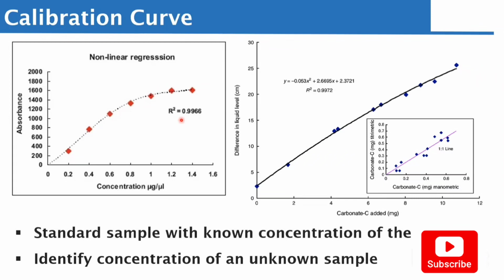And obviously, this leads me to also say that each control sample can come with its own calibration plasma or calibration sample, as the case may be. So one other reason why we repeat the calibration is if we find out that the lot number of the current control sample is different from what is already inputted and accepted in the system. It means you then need to redo another calibration which is consistent with the current control sample. I hope that makes sense. Let me repeat what I said. We repeat calibration when we say that your QC failed.